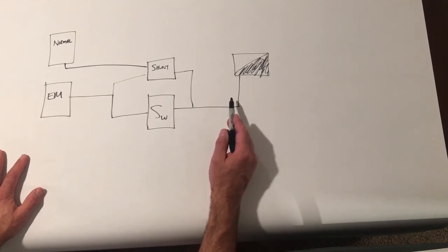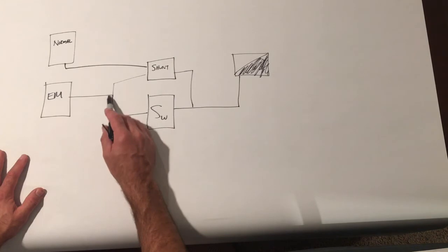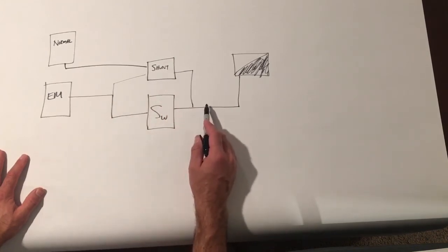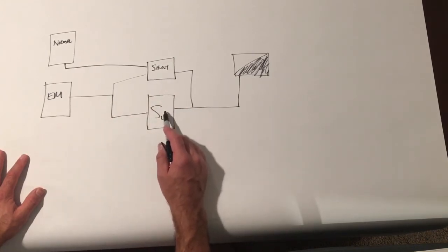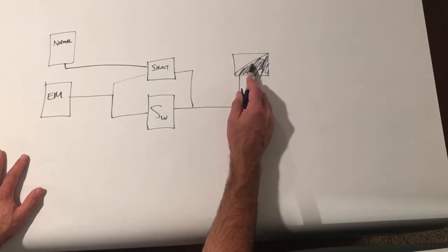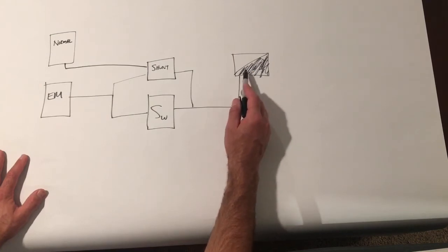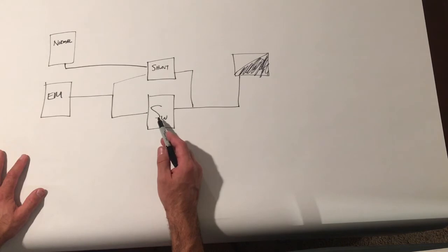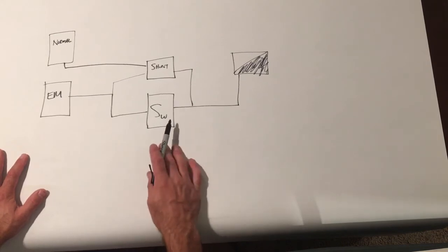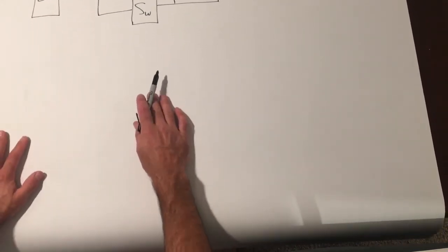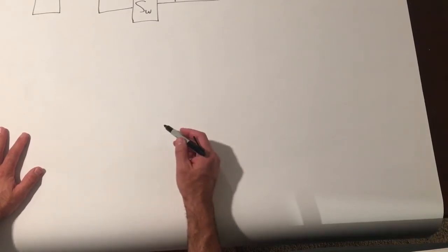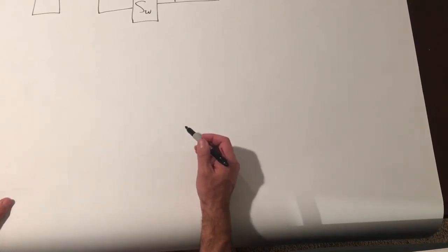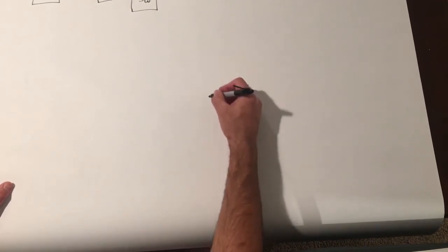The one drawback is because power is always flowing through this switch, we would need a separate switch to turn this fixture on and off. So if we get a room with 10 fixtures, nine normal and one emergency, we would need two switches. So that works, but not always the most user-friendly application. So I'm going to show you the next application where we can use one switch to control nine normal fixtures plus one emergency fixture.